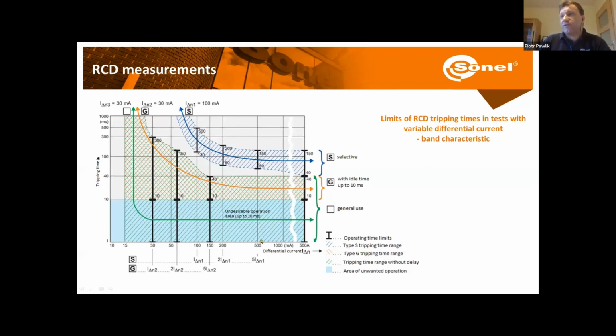So for the general use of this RCD, we will look at the green field here on the specs. So for example, when we have the rated current here, 30 milliamps, the disconnection time will be between 0 up to 300 milliseconds. As we increase the value of the current, the disconnection time will drop, but still starting from 0, just to the lower values.